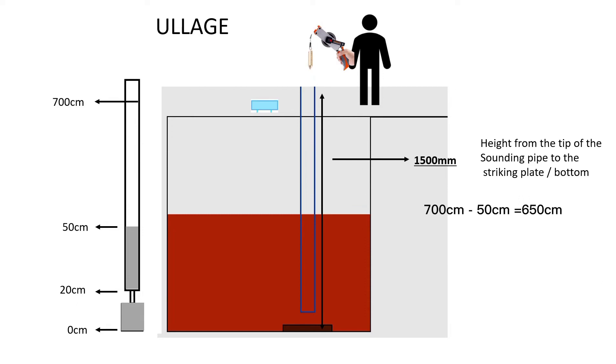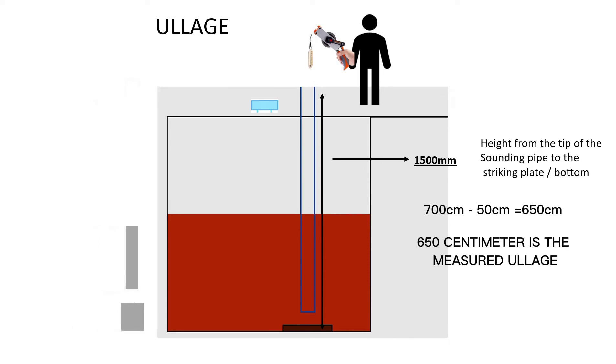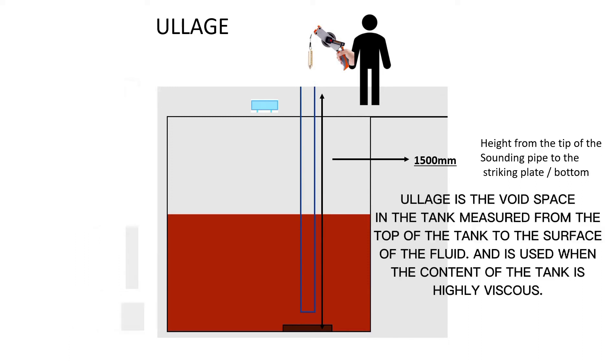To calculate for ullage value: roll down value subtract by measured value. 700 minus 50 equals 650. 650 centimeter is the measured ullage. Ullage is the void space in the tank measured from the top of the tank to the surface of the fluid and is used when the content of the tank is highly viscous.